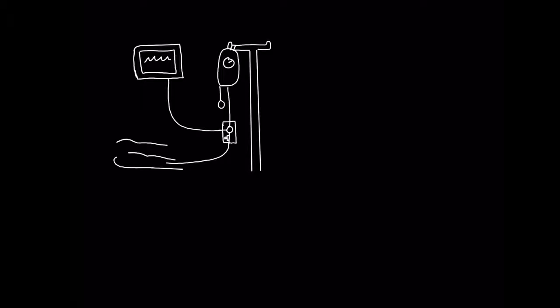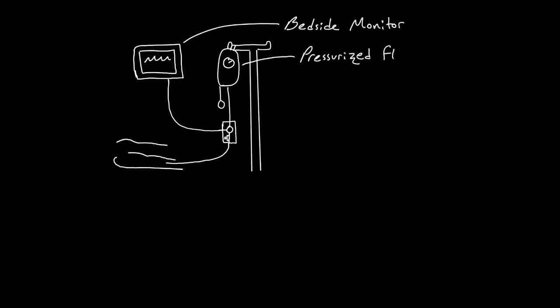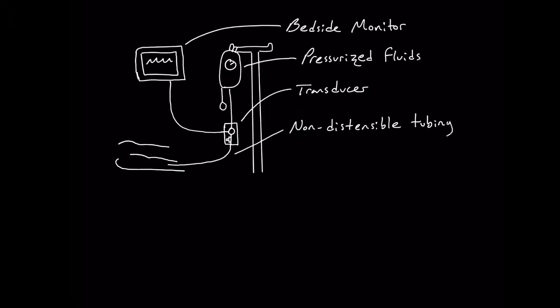In order to set up this system, you need a bedside monitor, a pressurized bag of fluids, a transducer which converts pressure into electrical signals that you can read on the bedside monitor, non-distensible tubing, and the line itself.